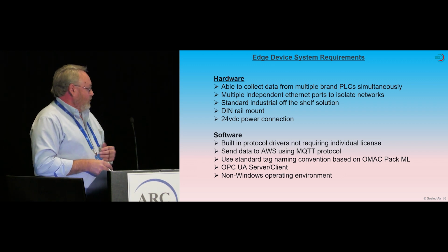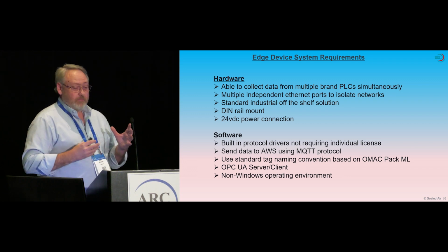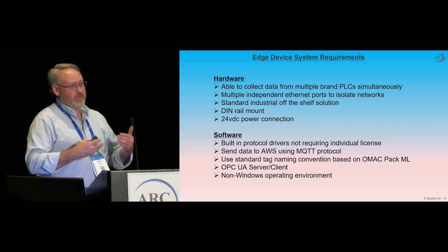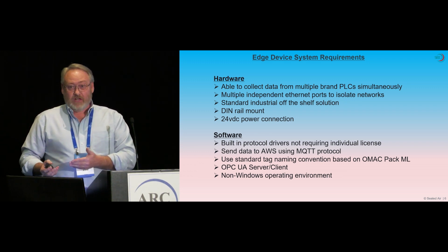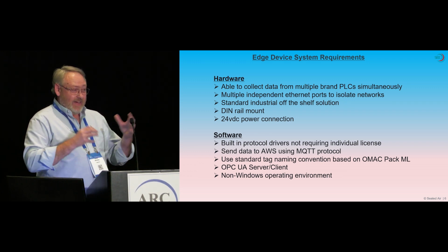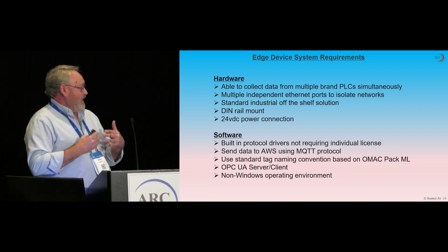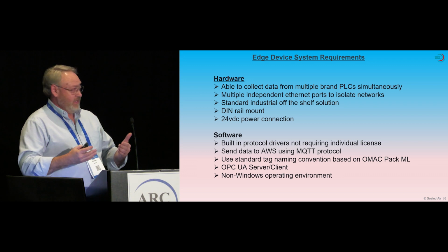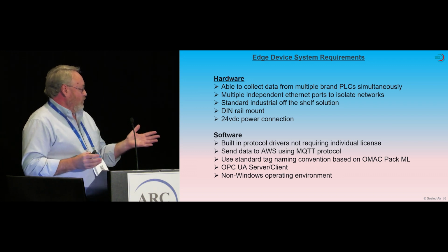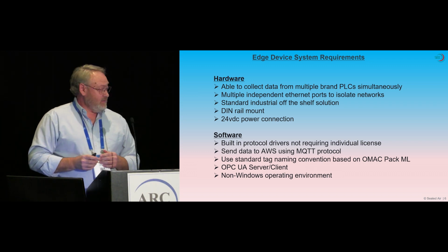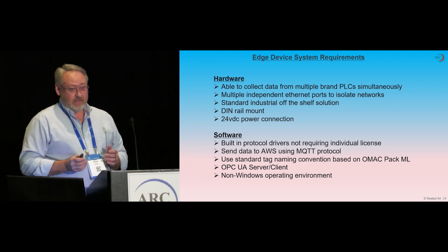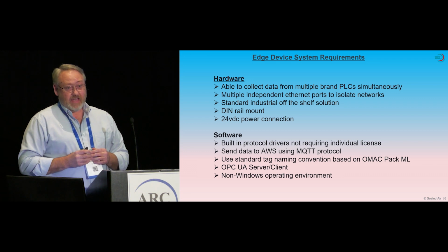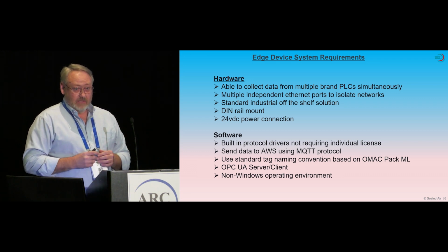From a software standpoint, we wanted something with built-in drivers. We don't want to have to pay a license for every single driver, for every single control system that we wanted to talk to. So we wanted something that would provide us that capability of talking to multiple pieces of equipment with multiple drivers already included. We wanted, of course, to be able to send data to AWS over MQTT. We wanted standard naming conventions for all of our tags based on PackML.